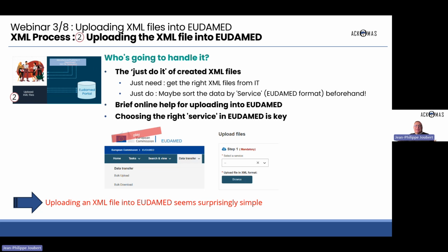You need to select the EUDAMED service, and I will come back to services in a few seconds. And you have to upload the XML file and then start the process. It's easy, okay? So uploading an XML file into EUDAMED, as I presented here, is surprisingly simple.